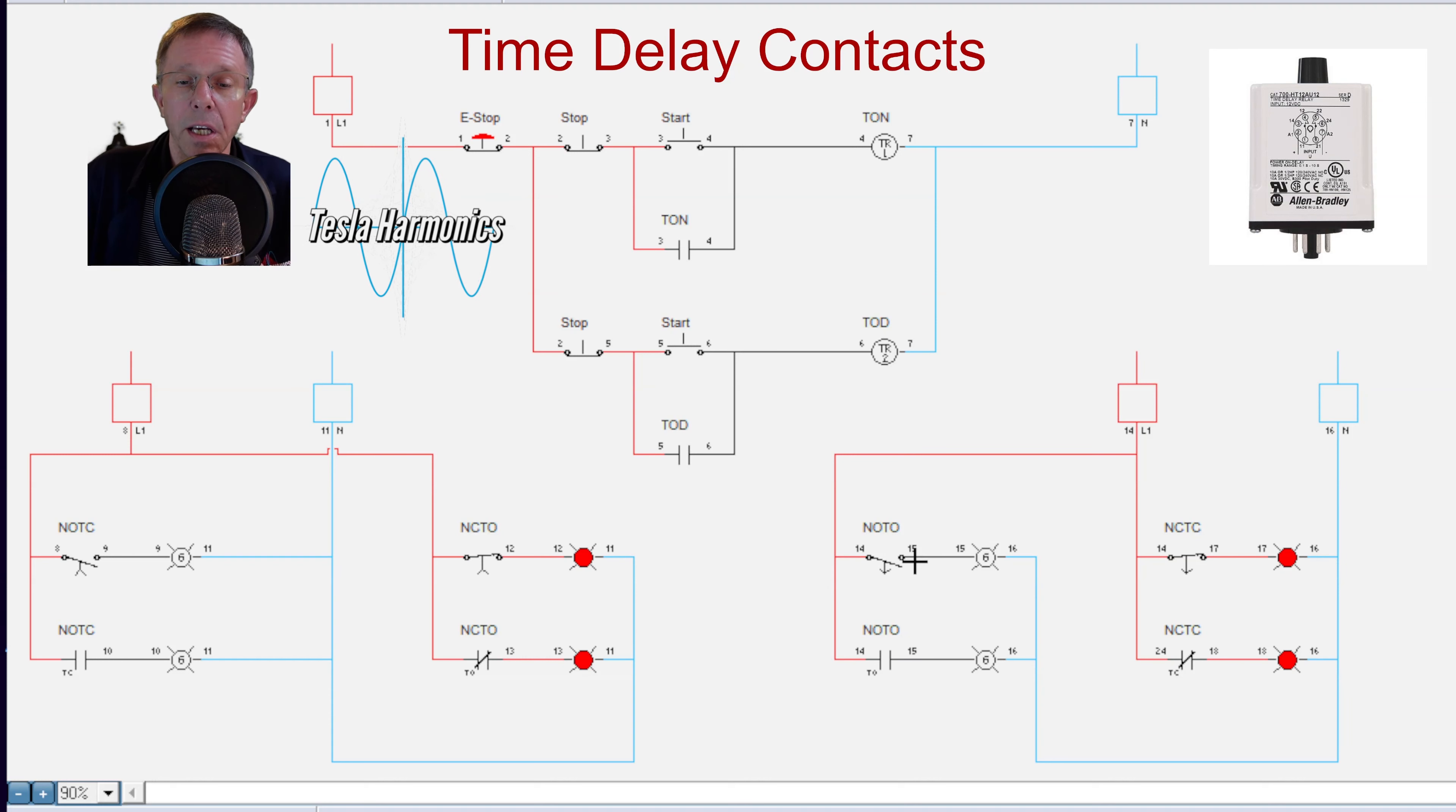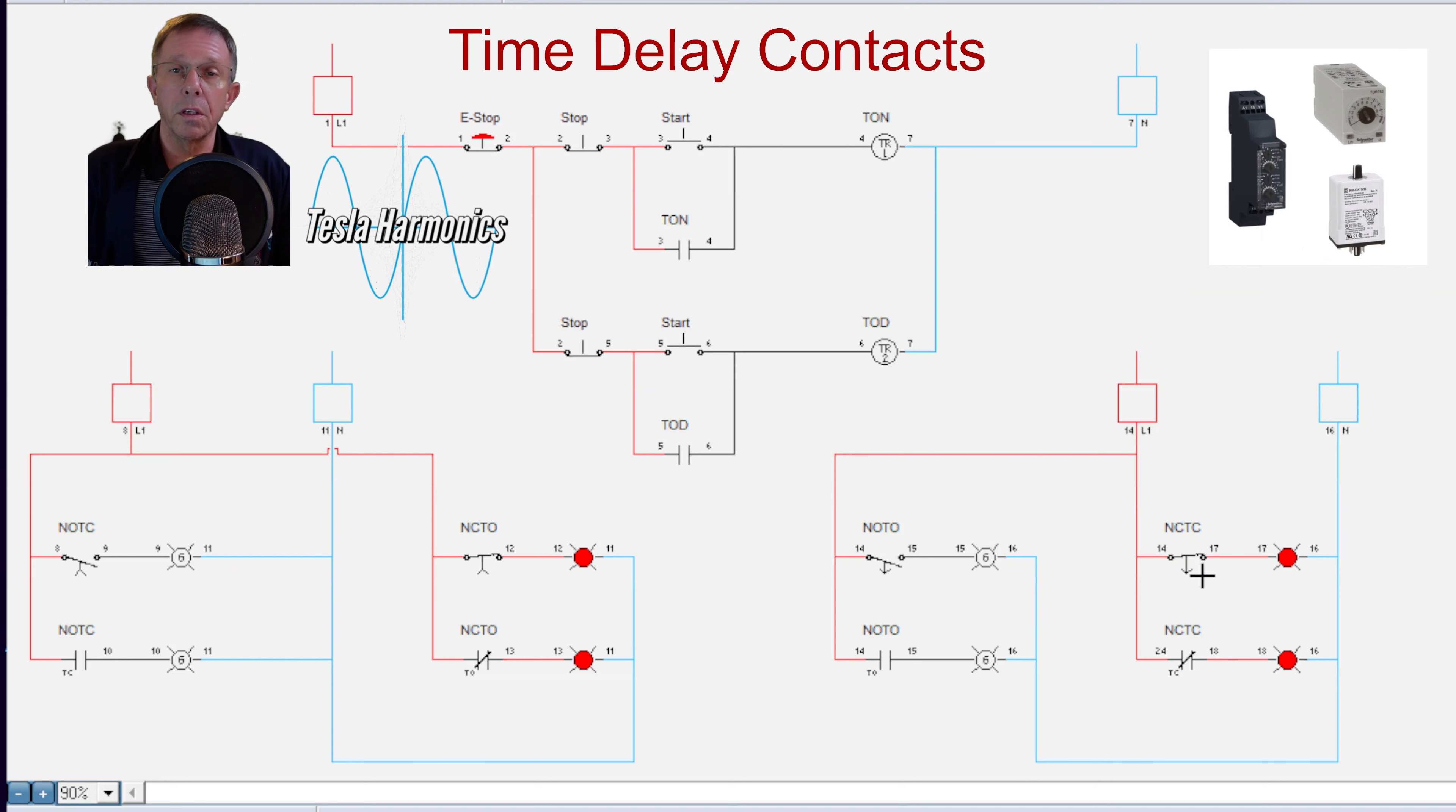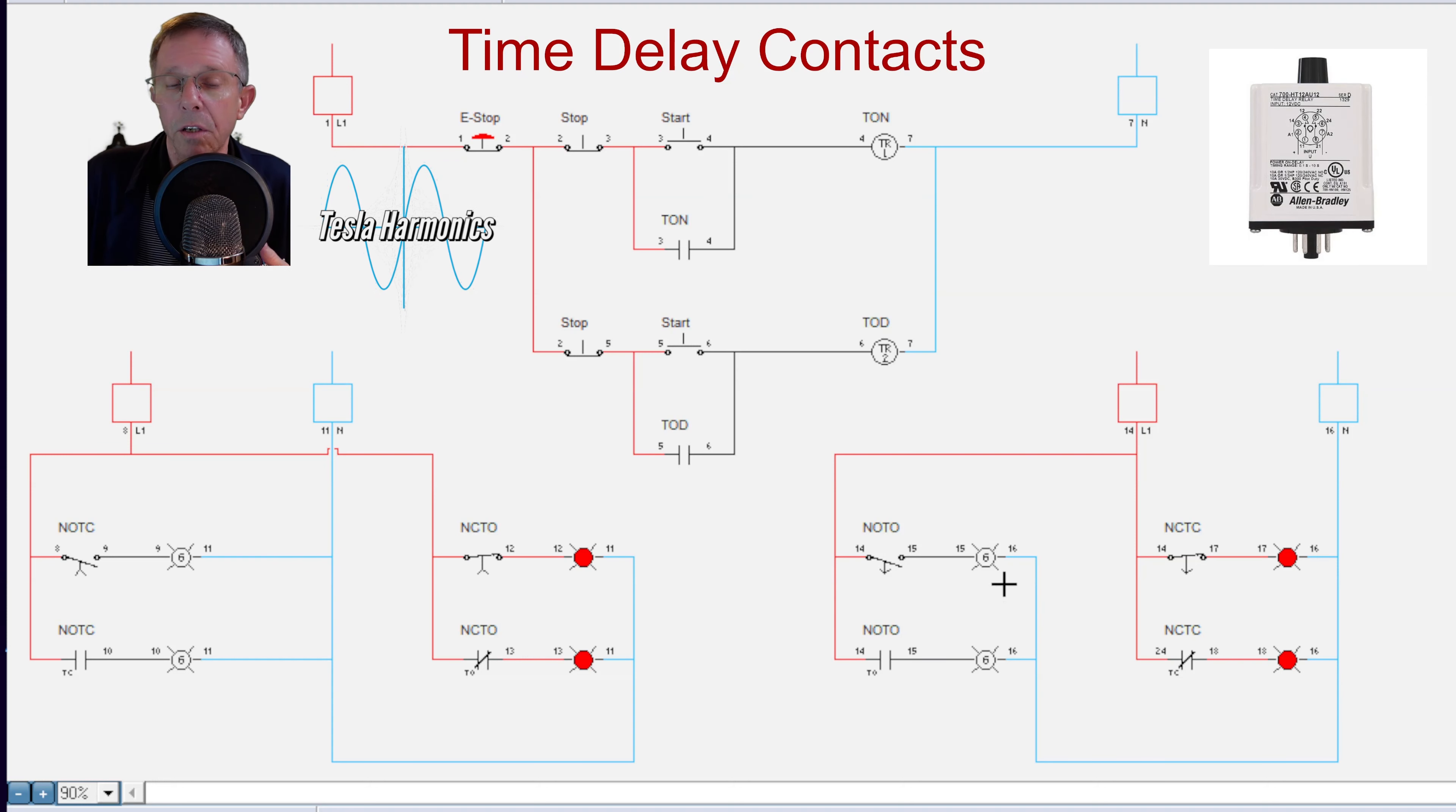And then when I kill power to that coil, then it's going to time before it drops out and turns off the green light. And remember, this contact does the same thing. This is just two representations of the exact same thing. With the normally closed on the time off delay, if I use those, they're going to be passing power to whatever they're connected to. And when the timer gets done counting for this one to go off, then these will go back on. All right, let's look at how that operates.